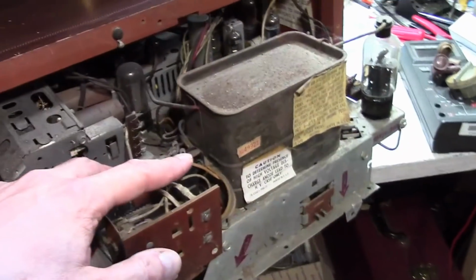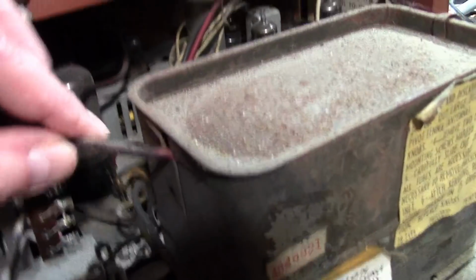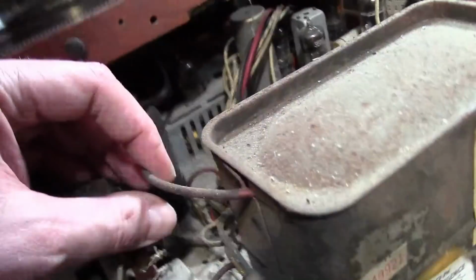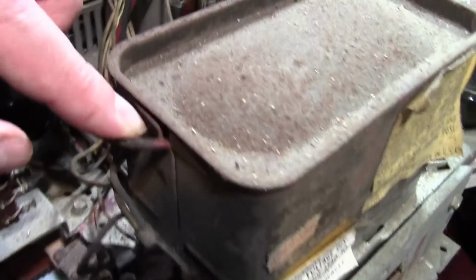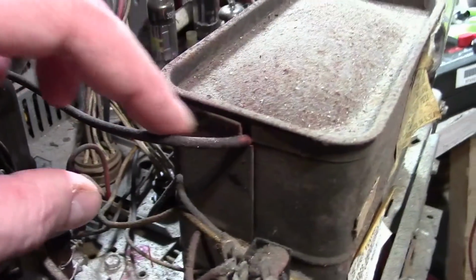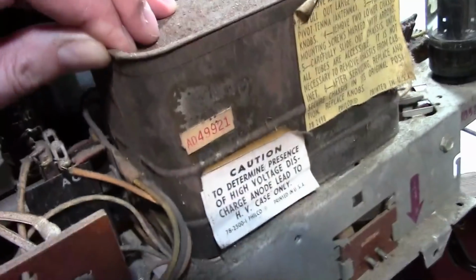Okay, what I did is I pulled off all the knobs, took off 2 sheet metal screws where those arrows pointed, and the whole thing pulls out to a point. Then the cable starts snagging, and I can tell you there's one thing wrong right away. This is the high voltage cable. It is not supposed to come out through a seam in the side of the high voltage box. It's supposed to go in through that hole down there. So I don't know what kind of moron did something like that.